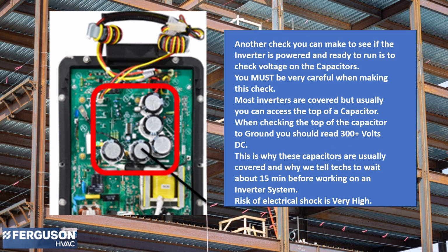Another check you can make to see if the inverter is powered and ready to run is to check the voltage on the capacitors. You must be very careful when making this check. Most inverters are covered, but usually you can access the top of a capacitor. When checking the top of the capacitor to ground, you should read 300 plus volts DC. This is why these capacitors are usually covered and why we tell techs to wait about 15 minutes before working on an inverter system. The risk of electrical shock is very high.